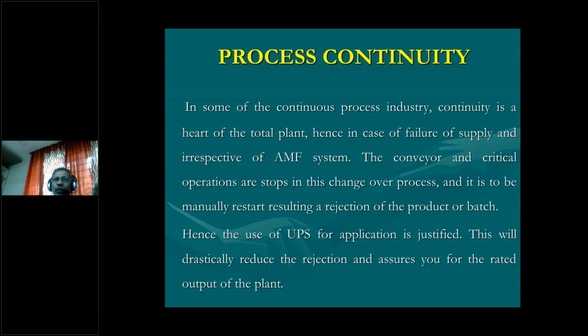So we have to select equipment for such an application, make a separate panel, and we always suggest going for a UPS. Yes, there will be a DG and an auto mains failure system. So on failure of supply, the DG will automatically start and the changeover will occur automatically. But that changeover may take some 30 seconds, depending upon the number of starting attempts. Suppose the generator could not start within one cranking, it may take more time. They don't accept that. In that case, we have to go for the UPS system.